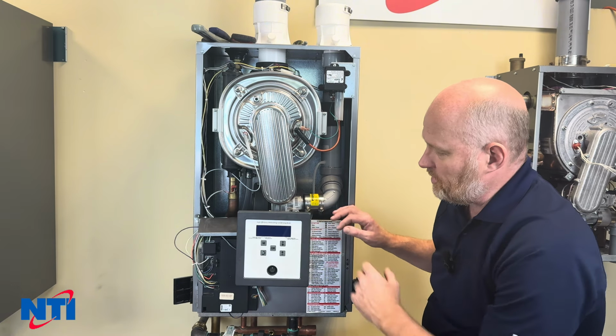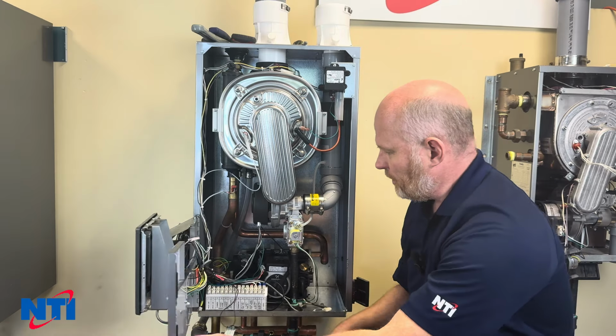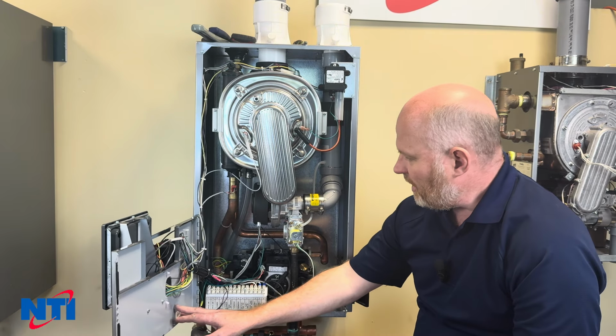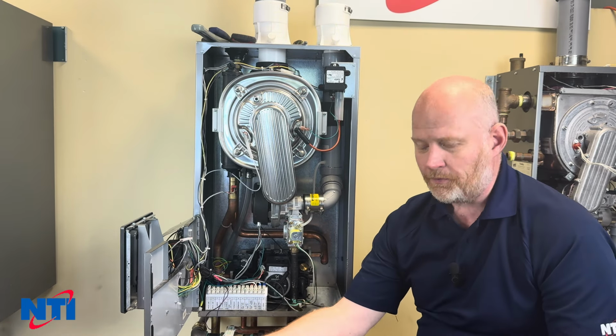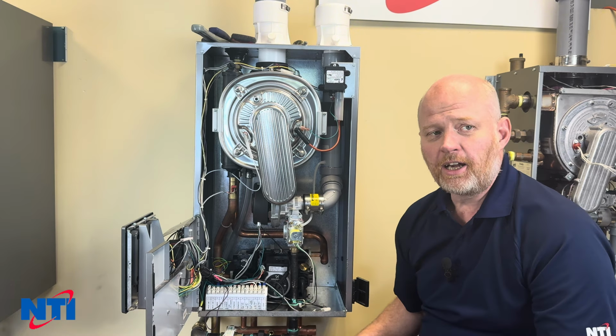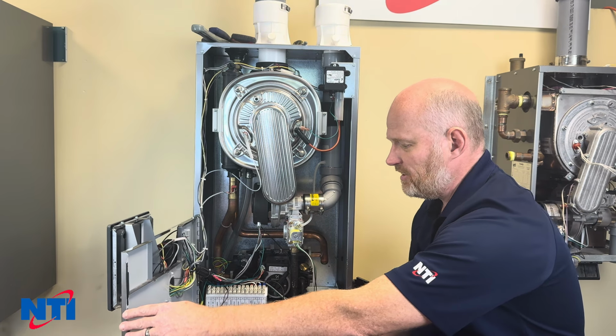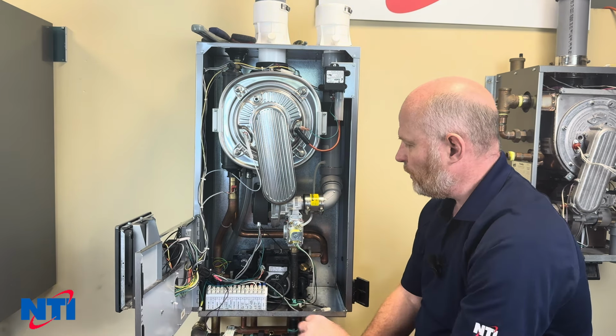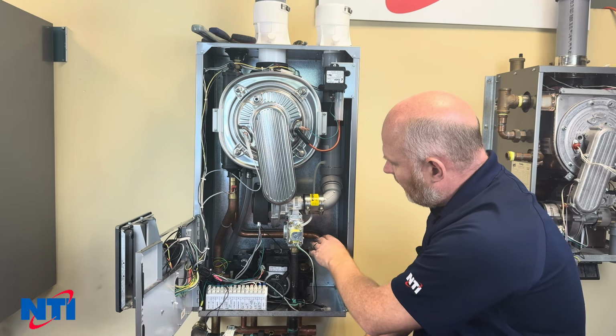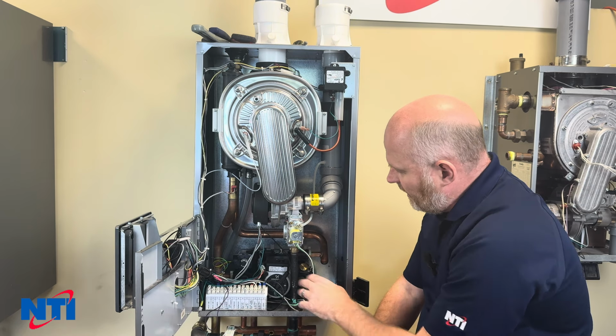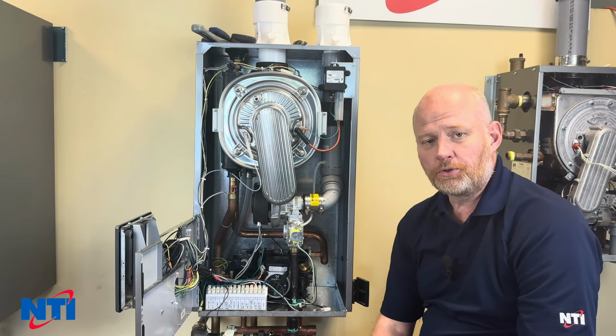Once you've done that, which this unit is already drained down, we're going to open up the cabinet. The door will swing off to the side. Just watch this if you're working down below it. I've bashed my head on that a couple of times, so make sure it stays swung back and look out before you lift your head. In the back here is the plate exchanger. It's held in place with only 2 screws.